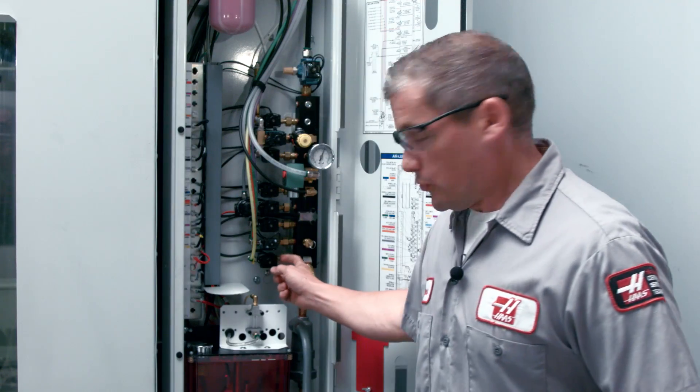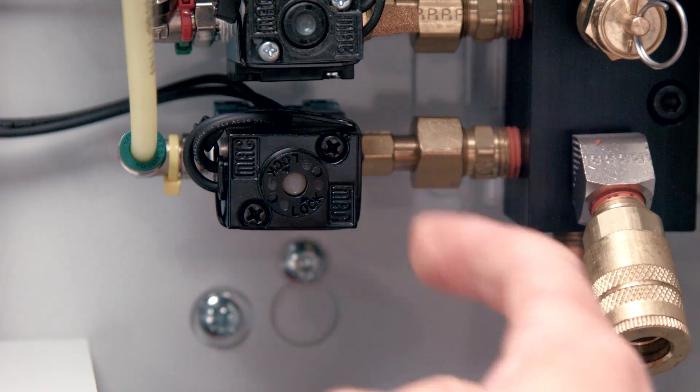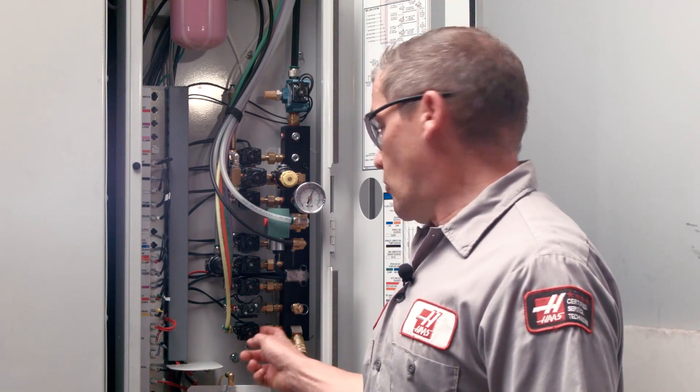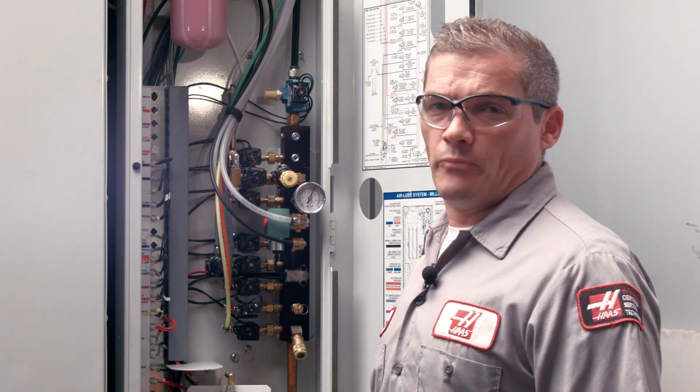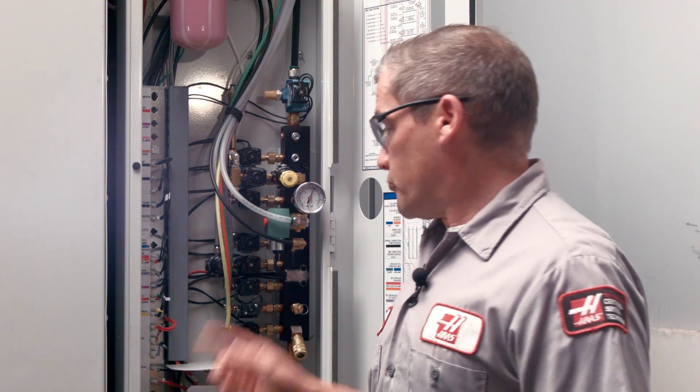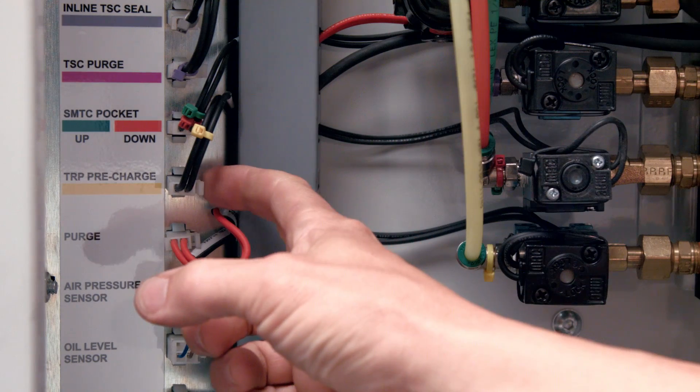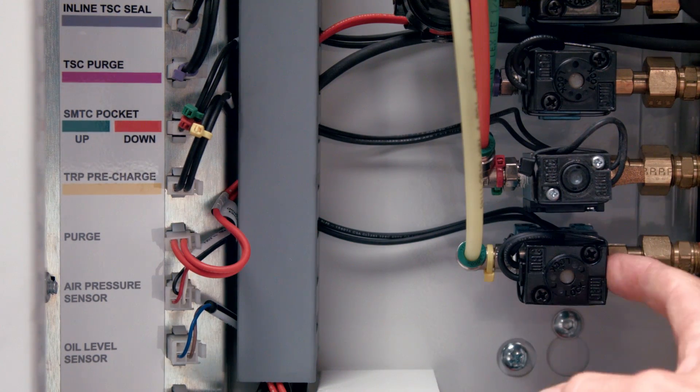Number one: is the solenoid receiving the correct electrical signal to turn it on and off? And number two: is the solenoid getting a sufficient amount of air and is it getting that air in a consistent manner? Let's consider a hypothetical example. Say I'm having problems with tool clamping and I suspect I have a problem with the TRP circuit. That leads me to check the TRP pre-charged solenoid right here.